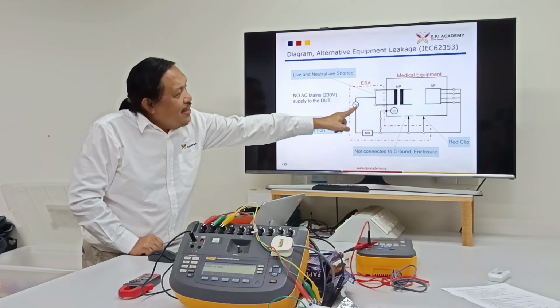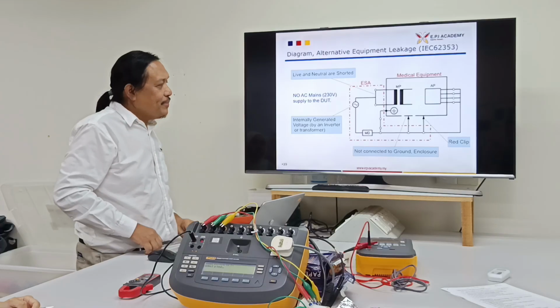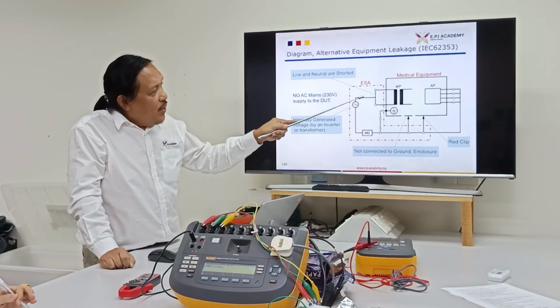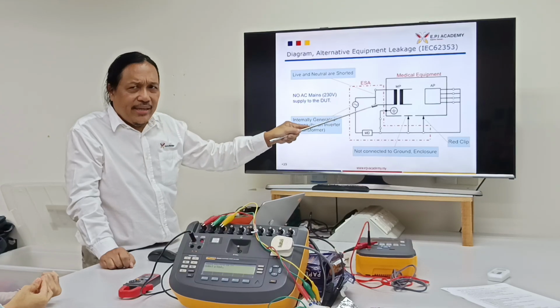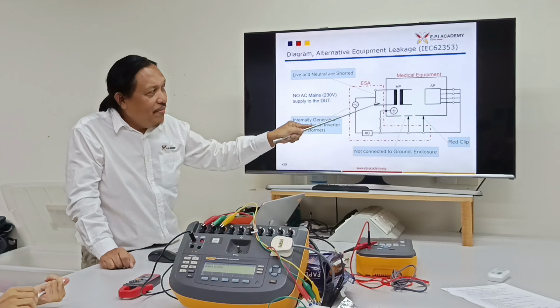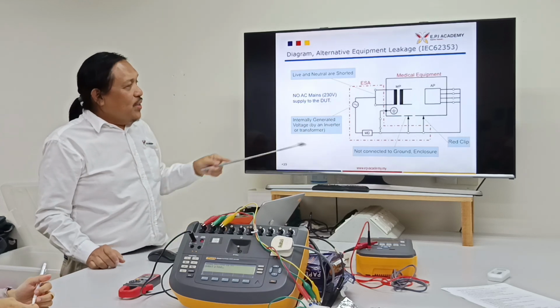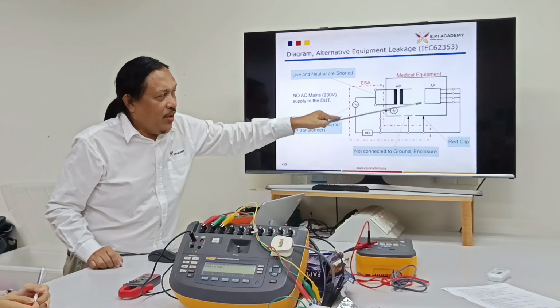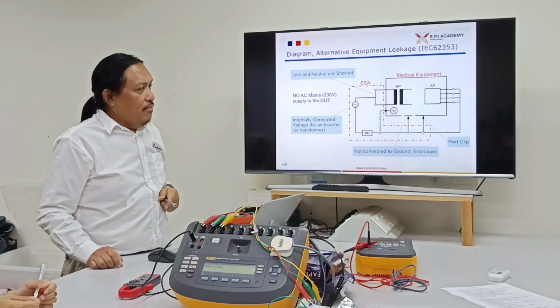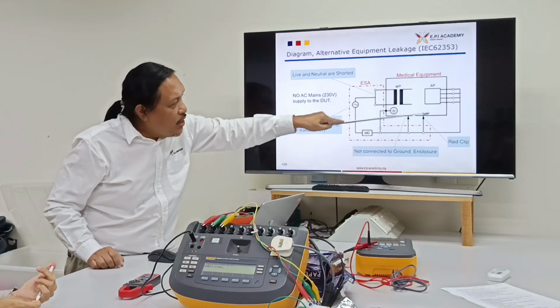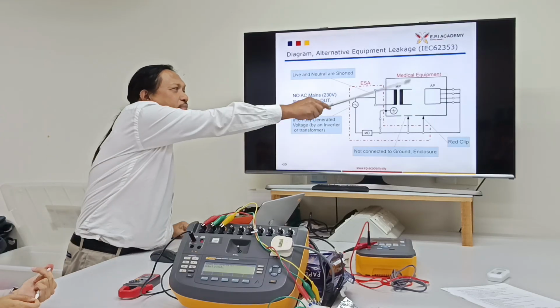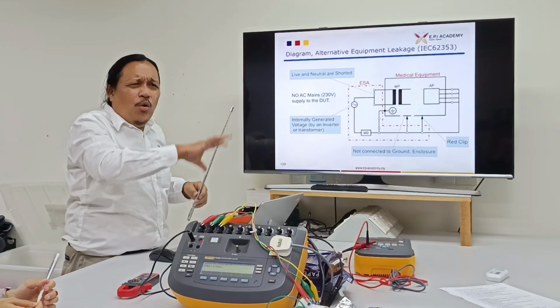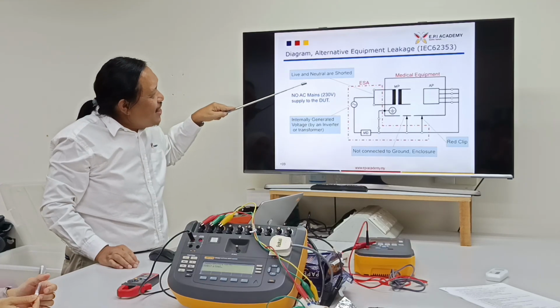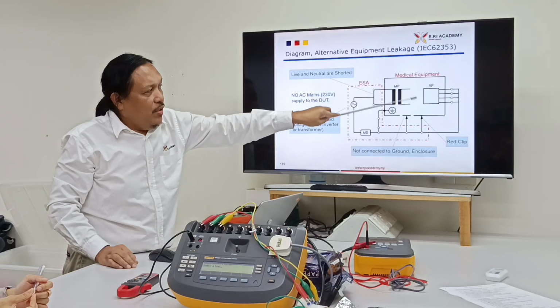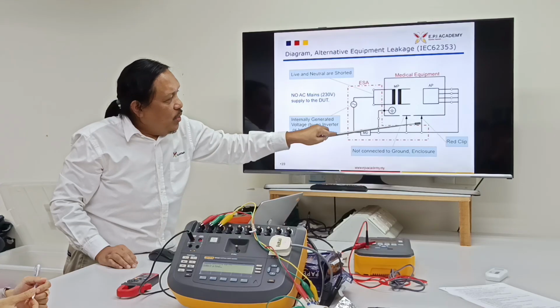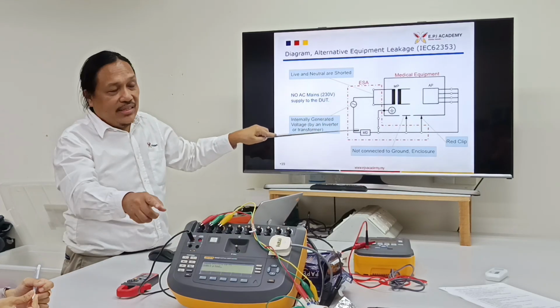So this Flow, this is a transformer. It's a small transformer like this, which will generate the test voltage. Connect this test voltage to the mains. What is mains again? Live and neutral. So that test voltage, of course, goes inside the equipment, and a current will flow because the insulation inside is not perfect. That test voltage will create a current because of the leakage inside the equipment. Of course, it will come out here, then is measured by the analyzer itself.